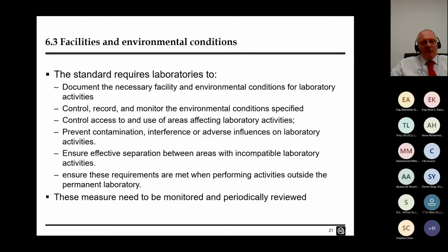We have to make sure that areas with incompatible activities are separated, and I've been doing this for 30 years, and I've still not really come across things that are incompatible, but you wouldn't want to be doing vibration measurements and mass measurements in the same laboratory or on the same bench. It's kind of self-evident, I think. So you have to make sure that activities which will affect each other are separated.